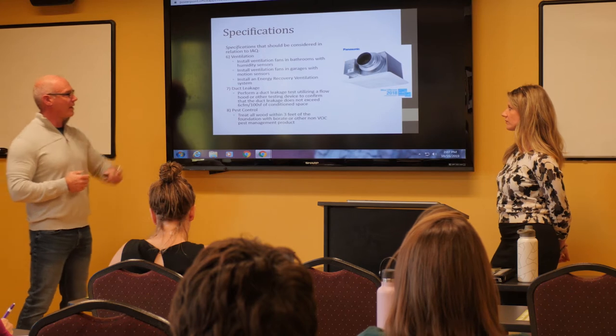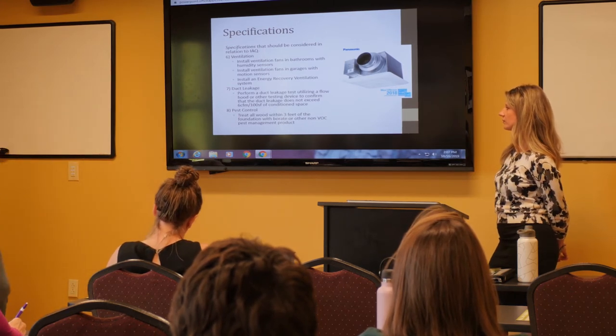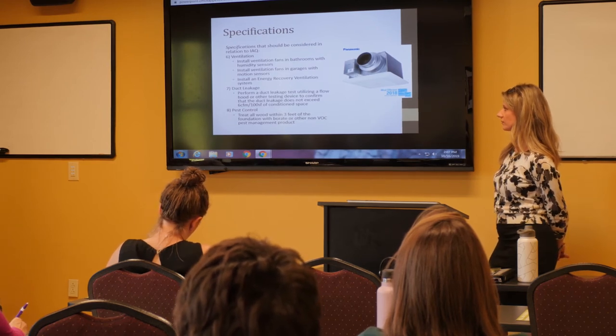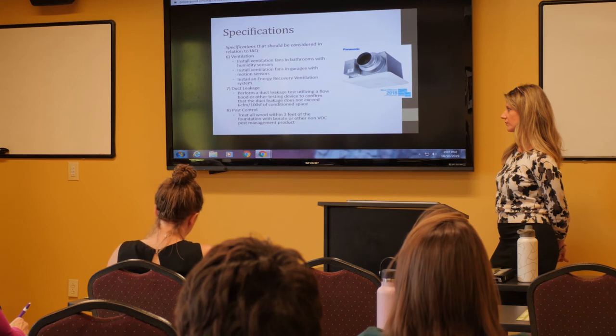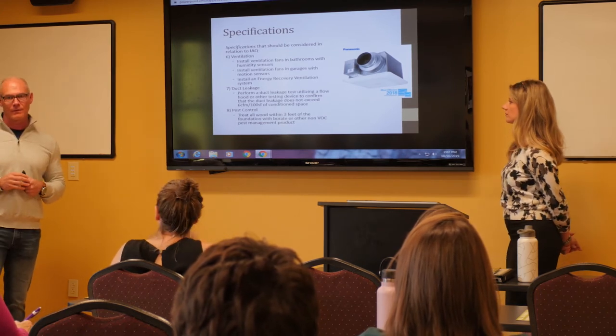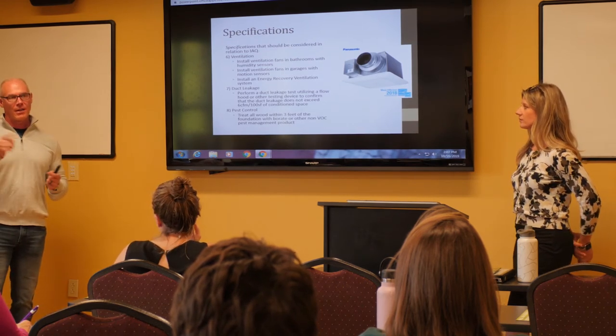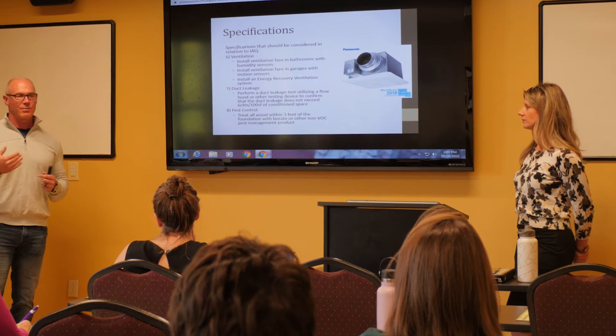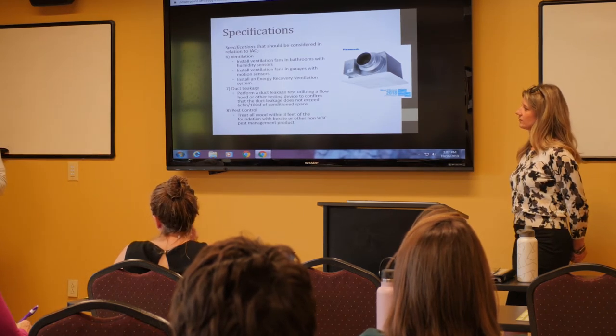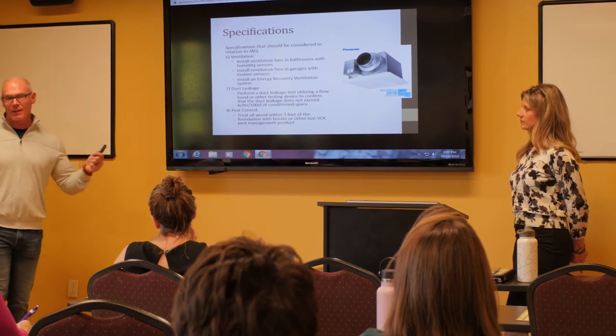And then there's an ideal ratio, not to exceed 6 CFM per 100 square feet of conditioned space. And they take care of all that, but that's why you want to hire a rater for you. Okay? Your rater will save you money the very first day they come on the job, I promise you. Amy or Jessica or anyone from our team will come on our job and they'll measure the insulation. And if we've specified 7 inches of open cell foam and it's 6.5, they'll call out the insulator and say, hey, get back over here and add extra insulation. And that right there saved us money.